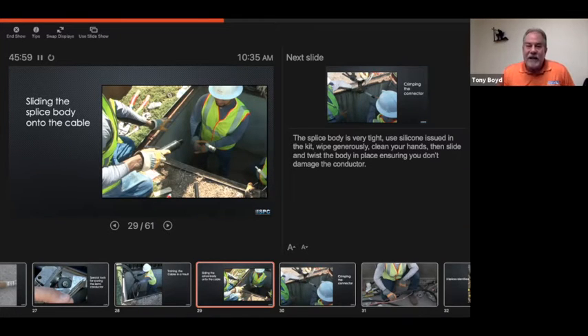Now, the splice body, this company requires using gloves, and it's always a good practice to use gloves when doing this. But I always let my guys do it barehanded. They would clean their hands. That way they would not get any dirt on the splice body. A lot of times our gloves get dirty and get contaminants on them.